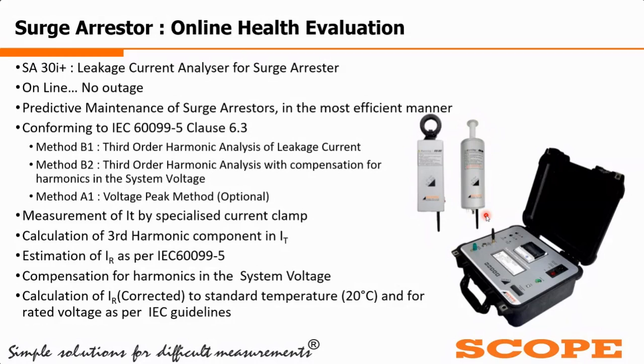You can also give the input of system voltage and relay LA rated voltage. This instrument will automatically calculate all the factors except only one factor, that is the manufacturer's design. Due to that, the percentage ratio between third harmonic and resistive leakage, that factoring is not possible automatically. For the other three parameters, the ambient condition, that is the temperature, the rated voltage, and the system voltage at the time of measurement, you can give them as a physical input to the kit.